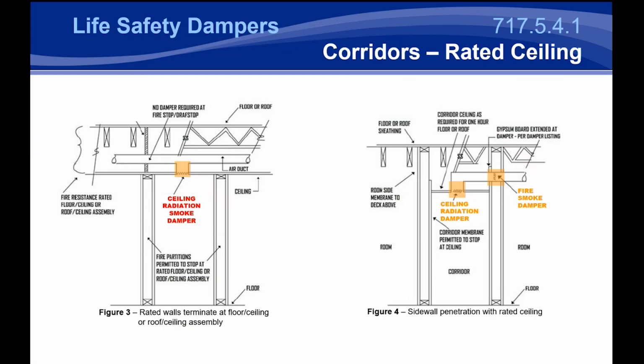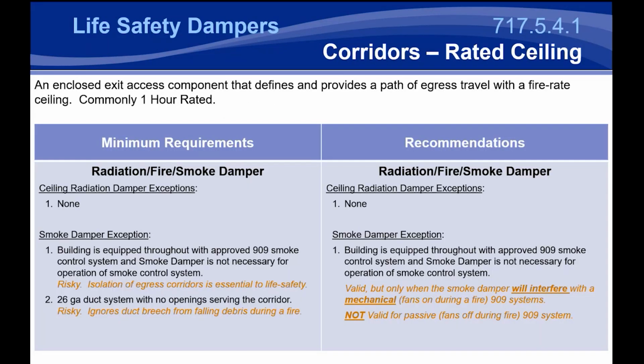Now, the next type of corridor has a rated ceiling. So any rated ceiling needs to be protected. That's throughout building code, whether it's a corridor ceiling or any other rated ceiling and any other floor ceiling assembly. With that, you do have to have some type of ceiling radiation damper protecting those openings. There are some ceiling radiation dampers that are certified as smoke dampers as well. They're typically only for T-bar type ceilings, so we don't recommend using those for most applications. For most applications, we recommend using a ceiling radiation damper in the rated floor ceiling, and then using your fire smoke damper in the sidewall penetrations.